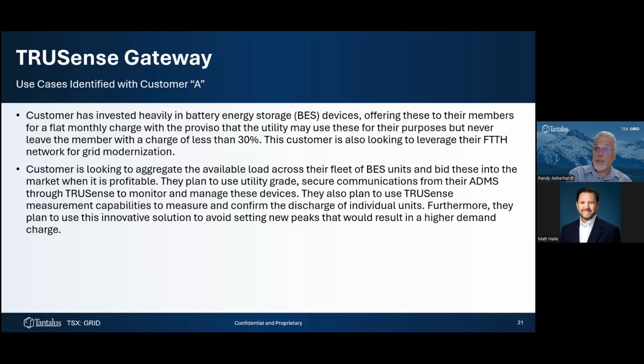Furthermore, they use the same solution to avoid setting new peaks, because in their environment, if they set a new peak, next year they'll have a higher demand charge. So they're very conscious they need to manage and monitor their peaks. When it looks like they're about to set a new peak, they'll immediately dispatch this fleet of battery energy storage units to avoid setting a new peak and avoid additional expenses or higher energy costs in the coming year. So it's very profitable for them.